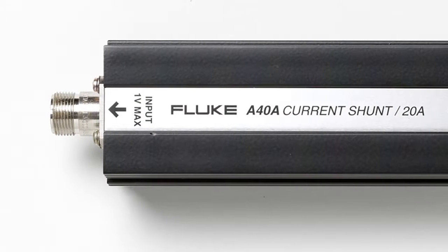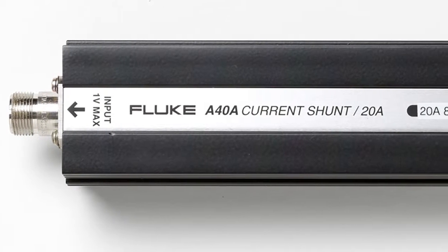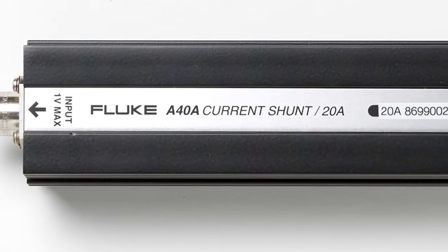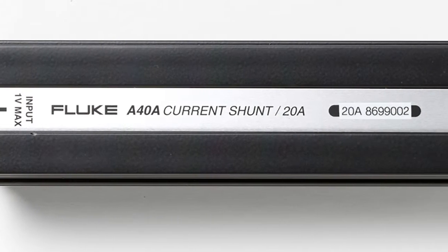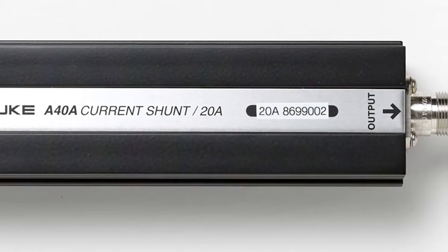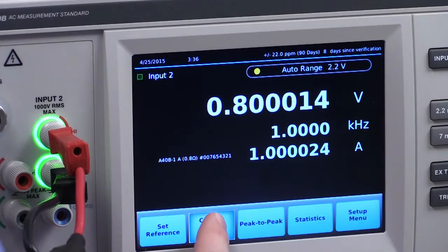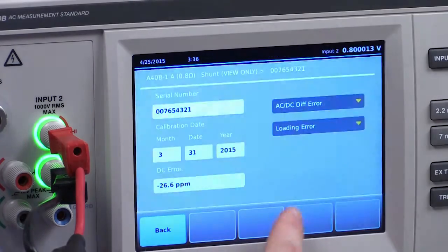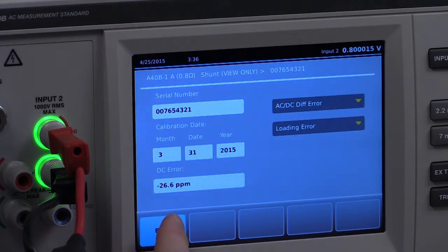Fluke A40 and A40A shunts can be used for relative current measurements. The 5790B can also use custom shunts that have been calibrated as a system along with the 5790B. The 5790B stores all shunt properties and coefficients which are used to calculate the current measurement.